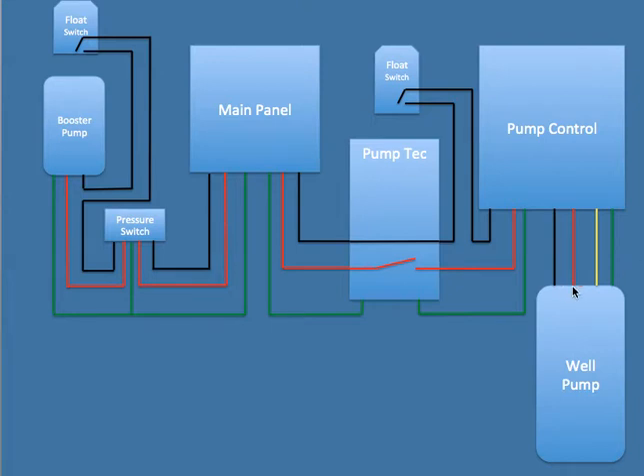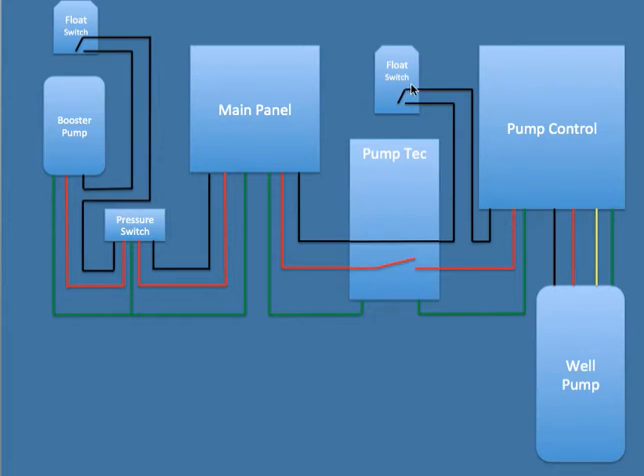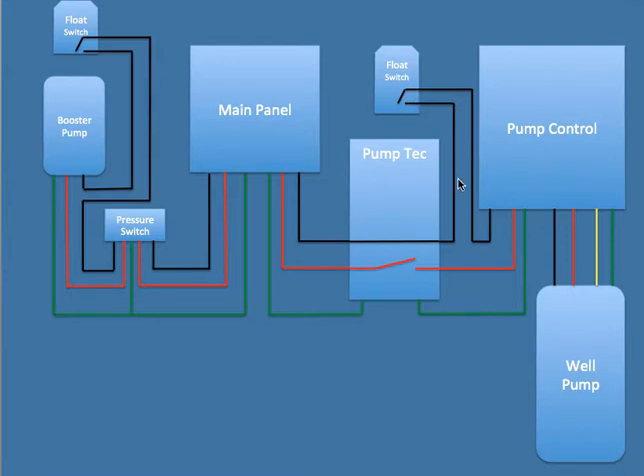So the well pump is connected to the control, the control is then connected lead two, lead one to the pump tech. In between lead one, I have a float switch at the top protecting overflow, so when the float switch is up, it'll disconnect the switch. When the float switch is down, it'll reconnect the system and allow the well pump to supply water into the tank.